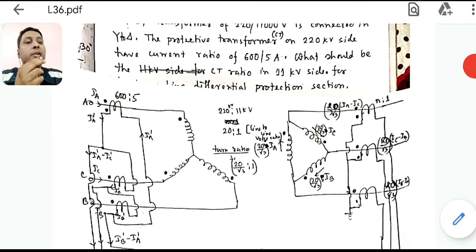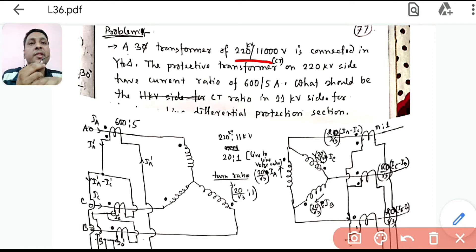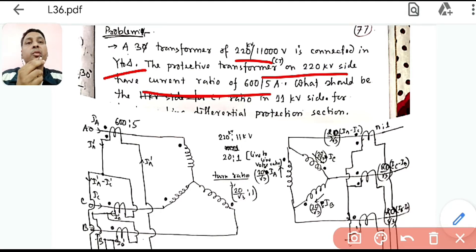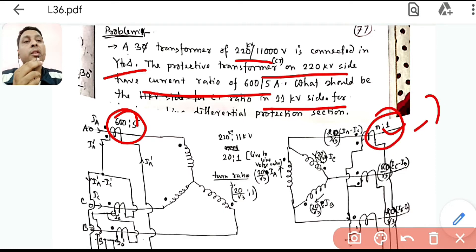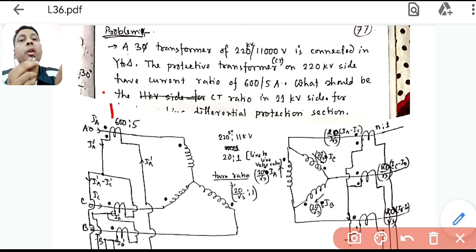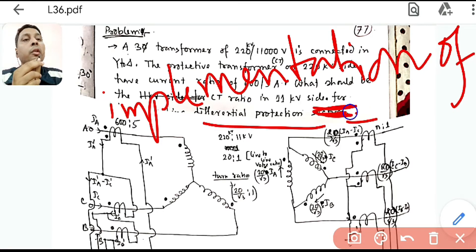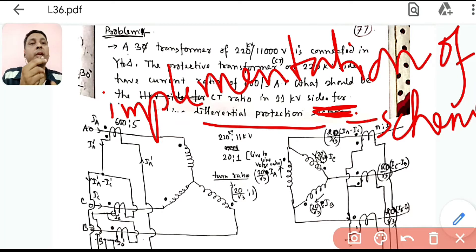The problem involves a three-phase transformer rated 220 kV by 11 kV. The primary side is 220 kV and the secondary is 11 kV, connected in star-delta. The CTs on the 220 kV side have a current ratio of 600:5. We need to find the ratio n:1 for the 11 kV side CT to implement the differential protection scheme.